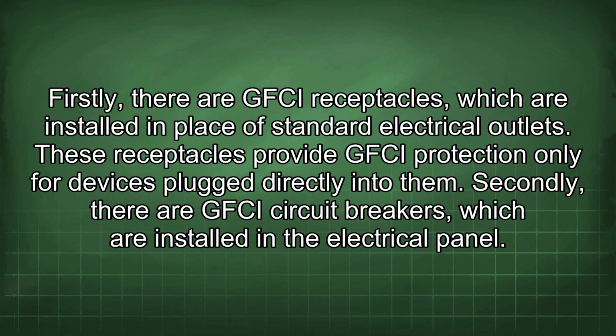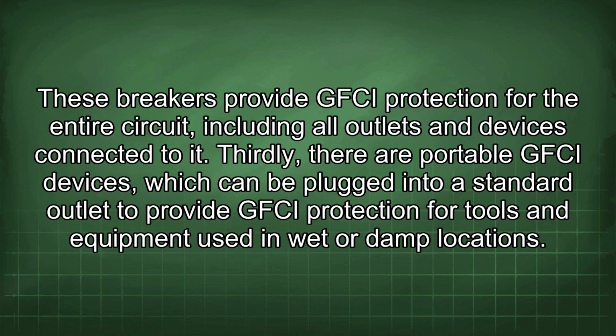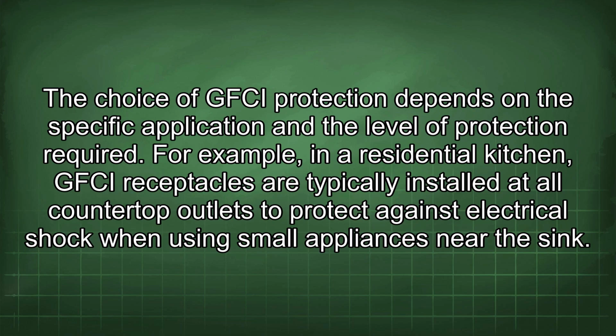Firstly, there are GFCI receptacles, which are installed in place of standard electrical outlets. These receptacles provide GFCI protection only for devices plugged directly into them. Secondly, there are GFCI circuit breakers, which are installed in the electrical panel. These breakers provide GFCI protection for the entire circuit, including all outlets and devices connected to it. Thirdly, there are portable GFCI devices, which can be plugged into a standard outlet to provide GFCI protection for tools and equipment used in wet or damp locations. The choice of GFCI protection depends on the specific application and the level of protection required.